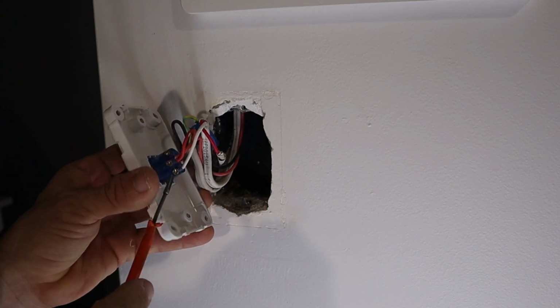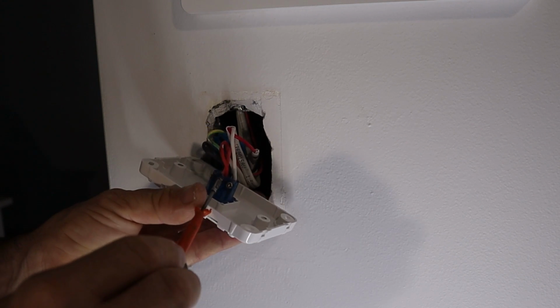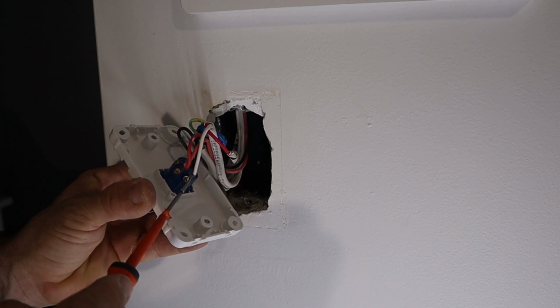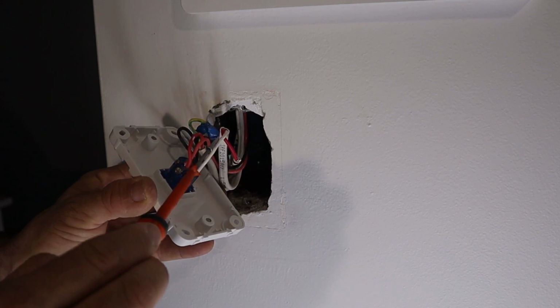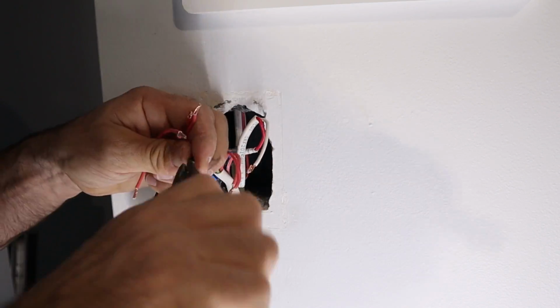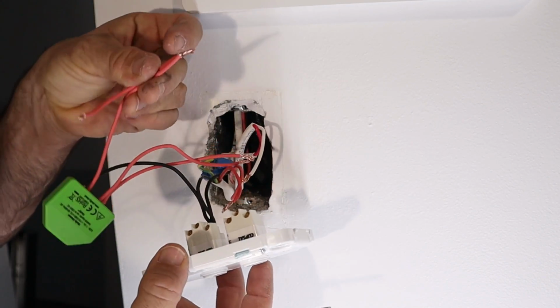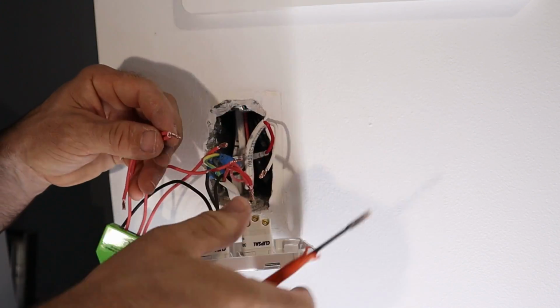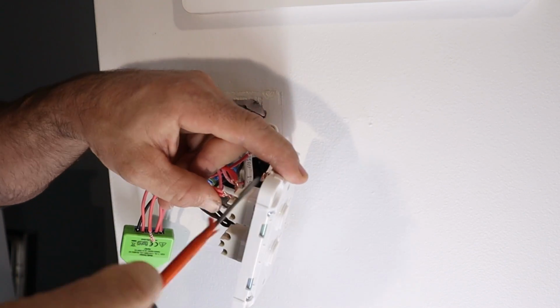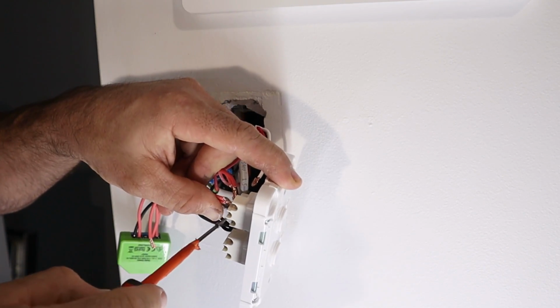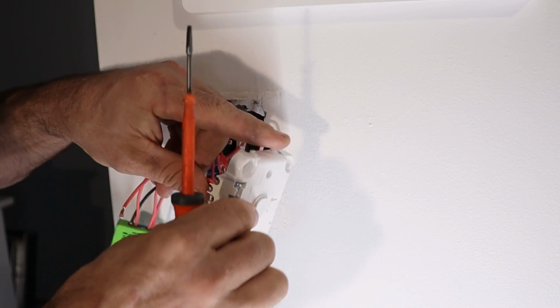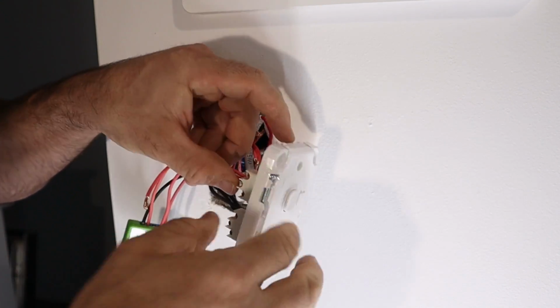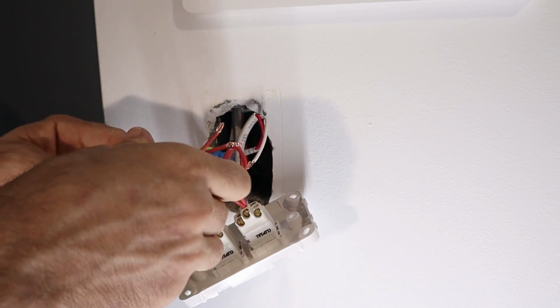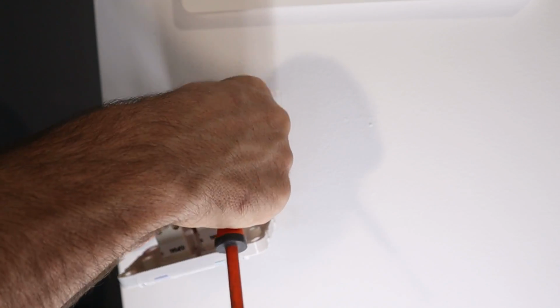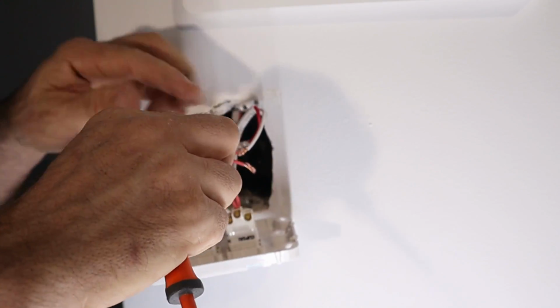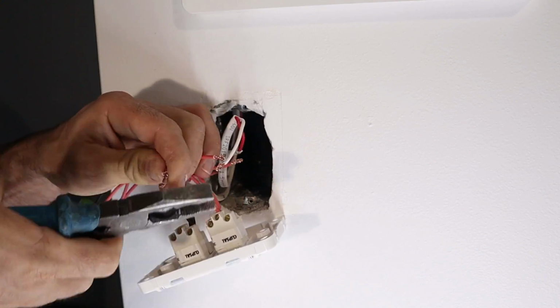So this switch is exactly the same as the other one we just looked at. It's a two-gang switch, except it's only got the active and the light switch. So the active coming in and the switch going out to the light. So we've got our active just here. And we're going to loop it to each of the common on each switch. And this is our active feed coming in.